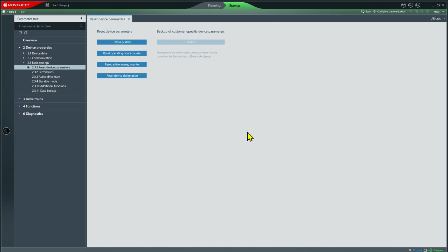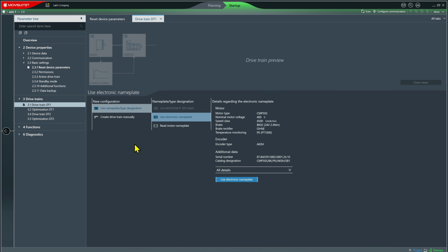To commission our VFD, we need to go to our drivetrains menu, expand it, and pick drivetrain DT1. There are actually two drivetrains called DT1 and DT2. We won't use DT2 for anything in this class. I will explain what the second drivetrain is for in a later session, but for now just pick drivetrain DT1. Open its page. Now, my particular motor, which is connected up, has an electronic nameplate. It's a servo motor, and it's got a hyperface encoder in it, which can include an electronic nameplate. There is one here. You can see it's been read right here.